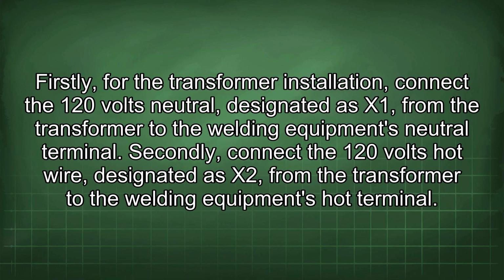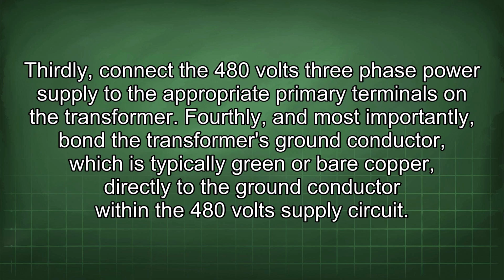Firstly, for the transformer installation, connect the 120 volts neutral, designated as X0, from the transformer to the welding equipment's neutral terminal. Secondly, connect the 120 volts hot wire, designated as X2, from the transformer to the welding equipment's hot terminal. Thirdly, connect the 480 volts three-phase power supply to the appropriate primary terminals on the transformer.